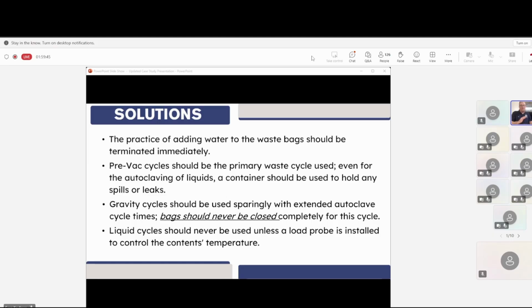If that steam doesn't even get in there at all or have any shot at it, you can forget it. Liquid cycles should never be used as a decontamination cycle. Put them in a container, and then they should not be used unless you have a way to monitor that load, because liquids, depending on how much, is going to change how much time. But if you do use the gravity cycles, I suggest at least 2.5 hours, especially if you're getting to larger loads, at least a 2.5 hour sterilization.